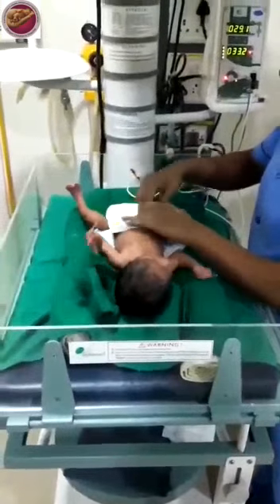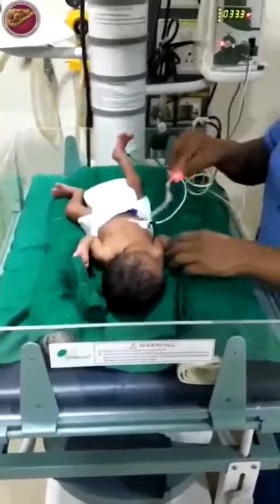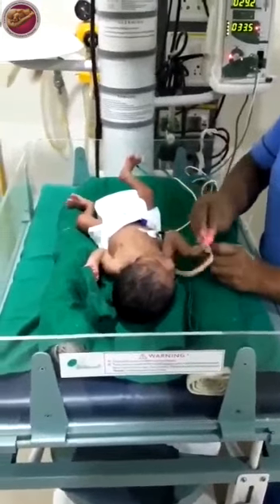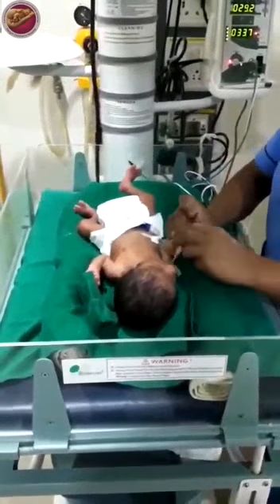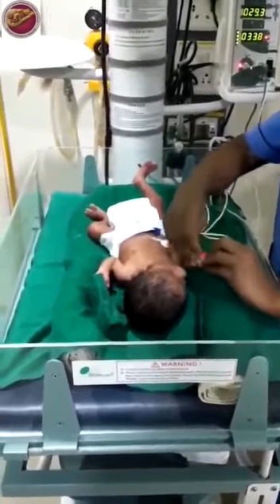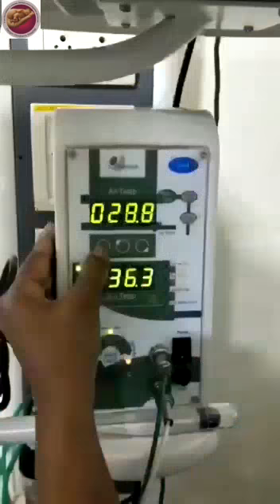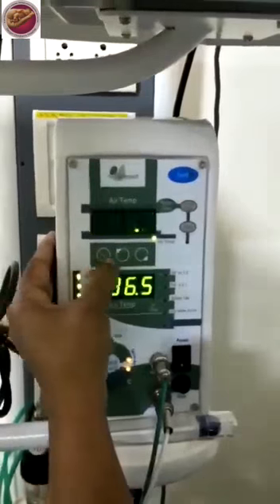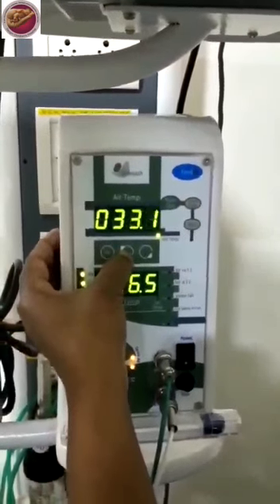Shift to servo skin mode and set the temperature of the skin probe between 36.5 to 37.5 degrees Celsius and the air probe setting as per the protocol on the ambient temperature from the chart. Record the temperature periodically as per protocol.